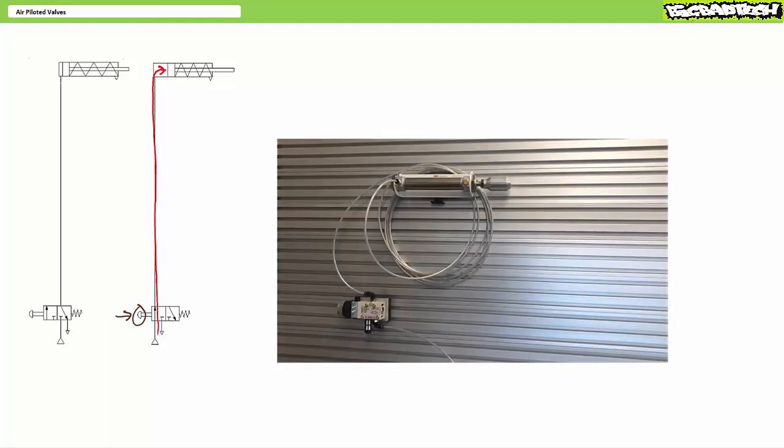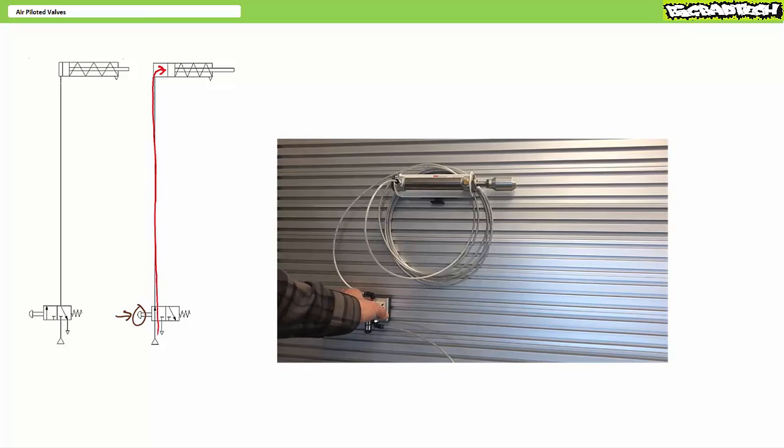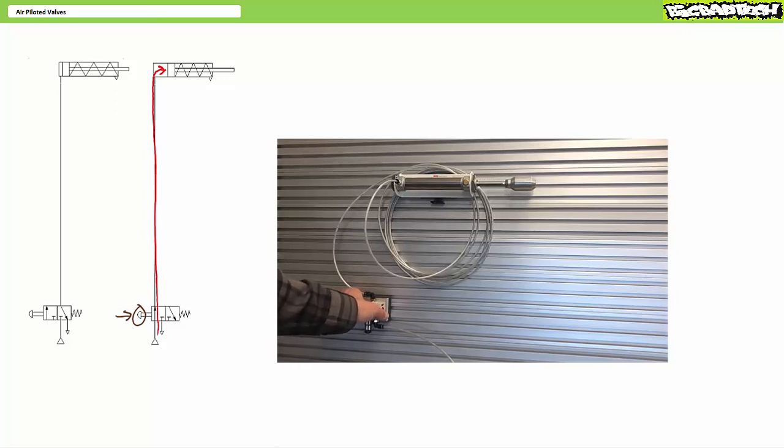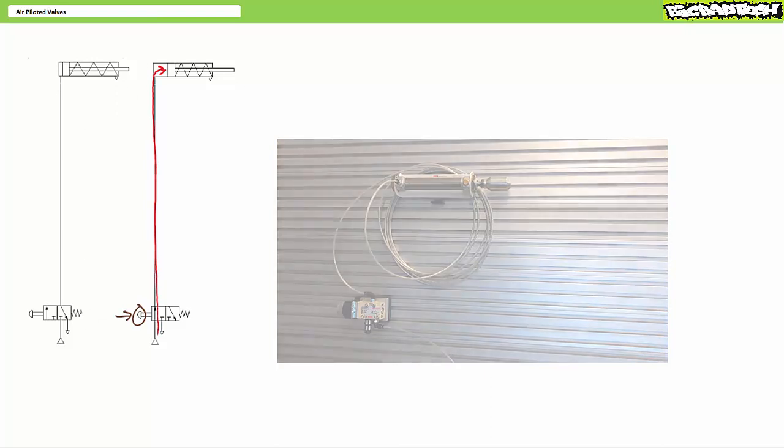Here's an example of this flawed system. I'm simulating the separation distance between the source and actuator with a huge coil of hose. When I press the push button, the cylinder does extend, but it does so with the eagerness of an eight-year-old shaking off a sugar rush the day after Halloween.